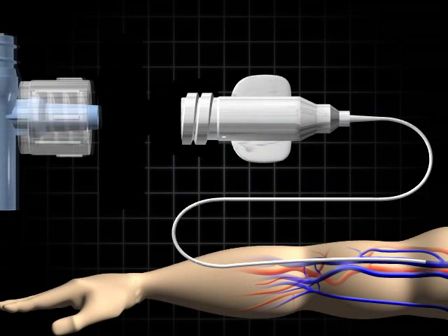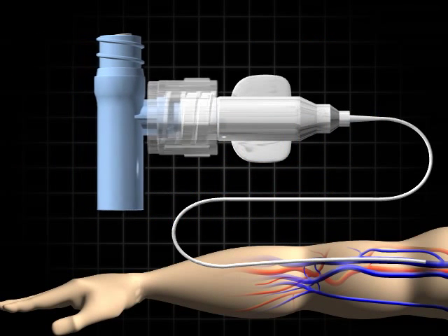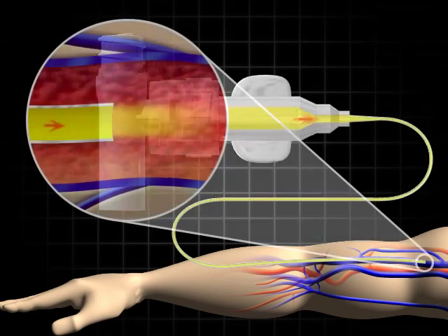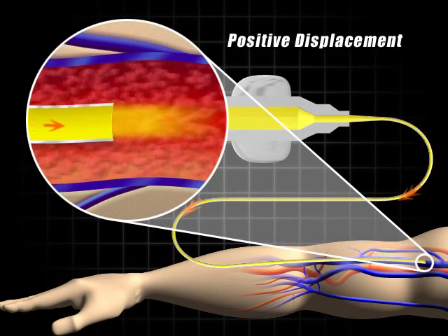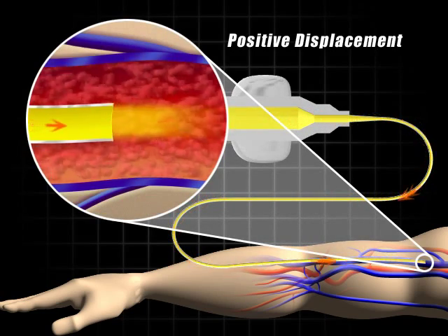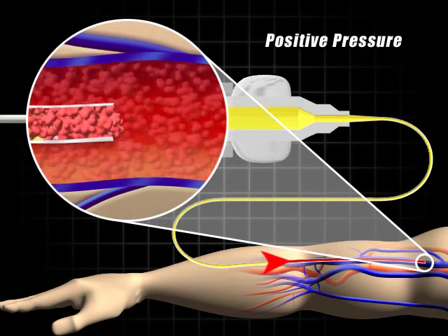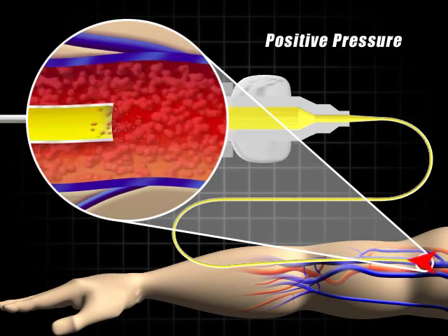The CLC2000 is the only device which guarantees positive displacement to eliminate any reflux of blood into the catheter lumen upon disconnection. Positive displacement is the complete displacement of potential blood reflux, where the end result is different from positive pressure, which may not completely displace the blood reflux.